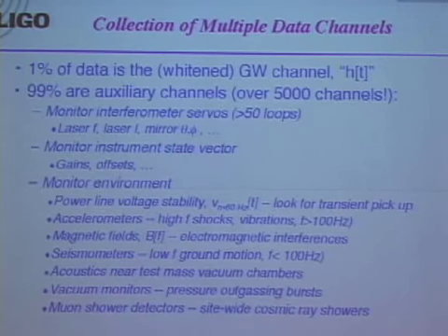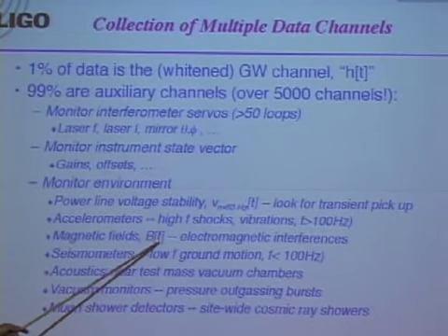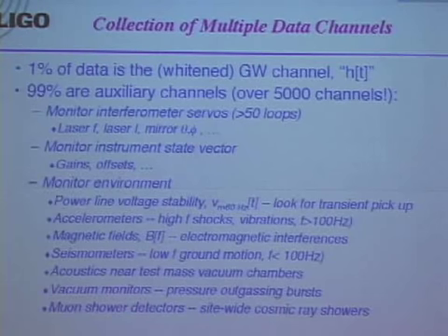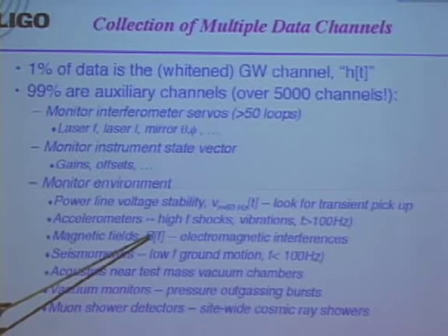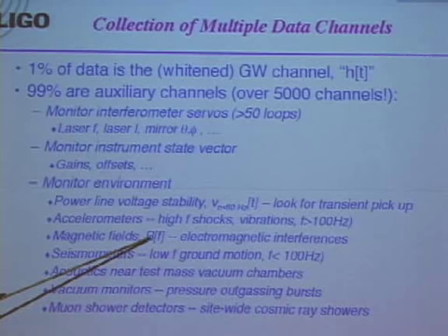The accelerometers provide high-frequency shock and vibration measurements above about 100 hertz. Magnetic fields are a concern too, so we have magnetometers that look for time-dependent fields, such as those that might occur in a building when motors are turned on and off.